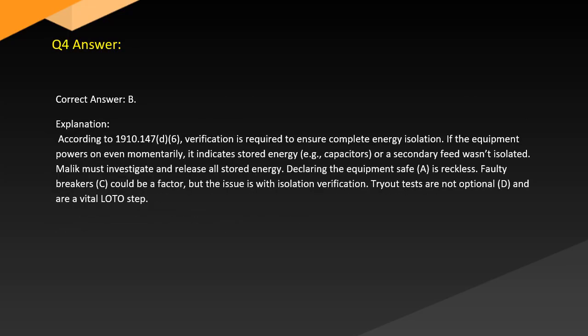Answer. Correct answer: B. Explanation. According to 1910.147 D6, verification is required to ensure complete energy isolation. If the equipment powers on even momentarily, it indicates stored energy, e.g. capacitors, or a secondary feed that wasn't isolated. Malik must investigate and release all stored energy Declaring the equipment safe, A, is reckless. Faulty breakers, C, could be a factor, but the issue is with isolation verification. Tryout tests are not optional. D: a tryout is a vital LOTO step.